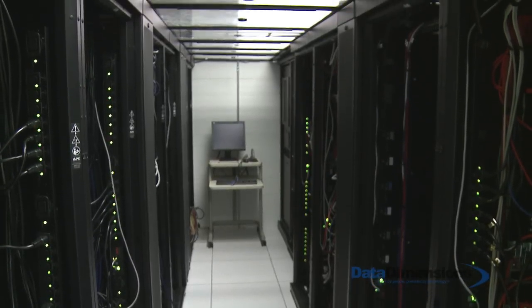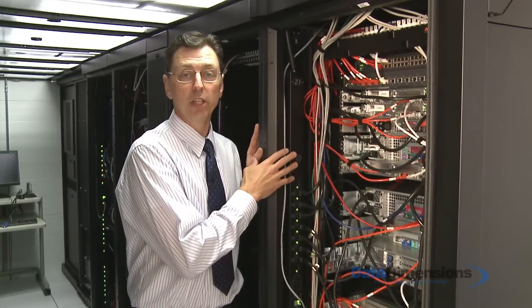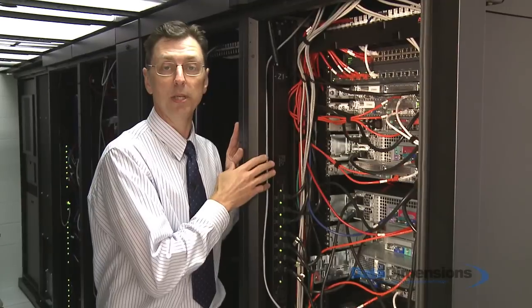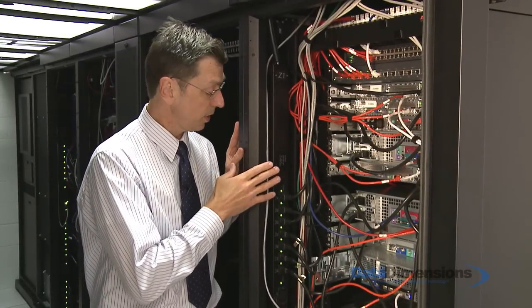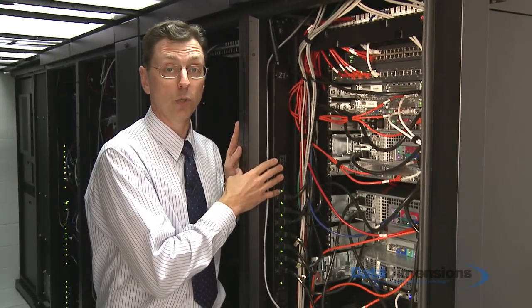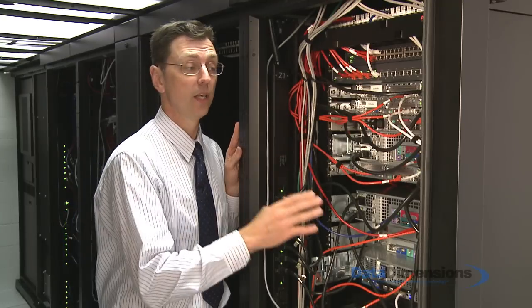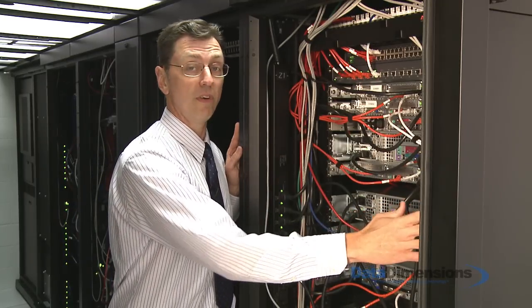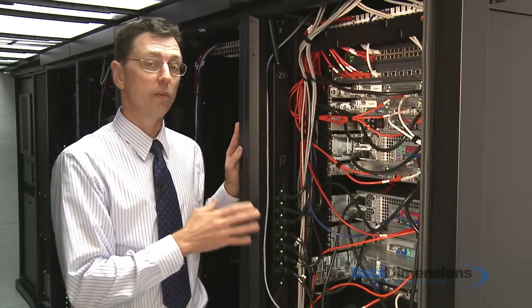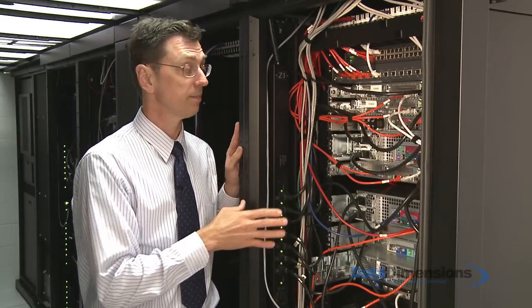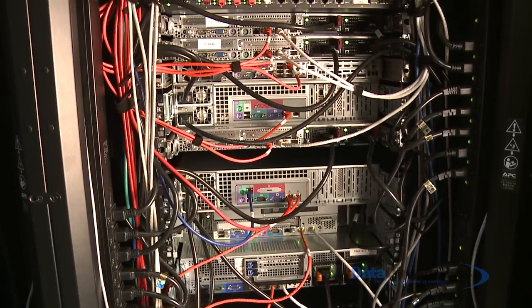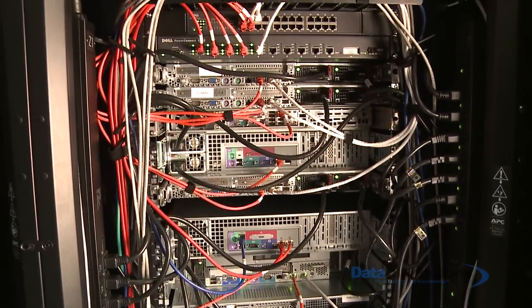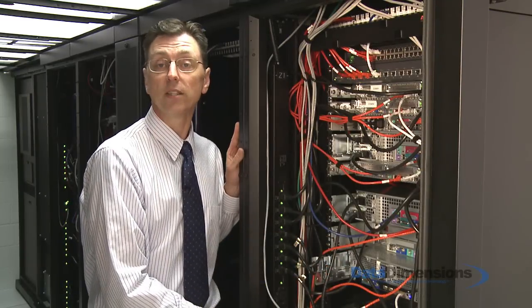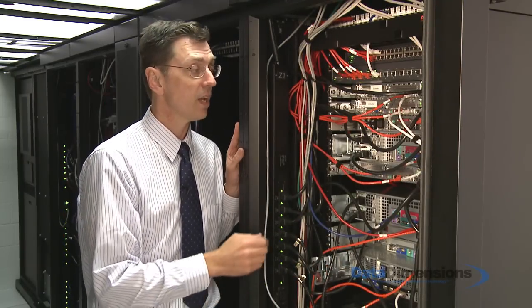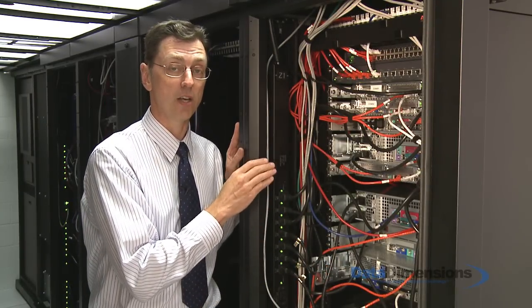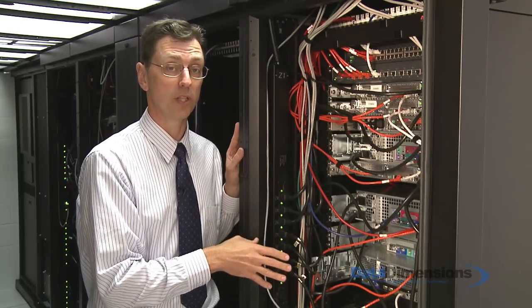Here we are in the hot aisle. Power coming into the back of each rack is supported off of separate APC UPS systems. The one that we saw inside the electrical room provides power to the left-hand side of the rack. The other, which is in row, provides it to the right. We have a similar structure for our cabling. Data connections are primary in red, secondary is in whites, managements are blues, blacks are for storage. This provides redundant capabilities as far as connectivity for all systems within the space.